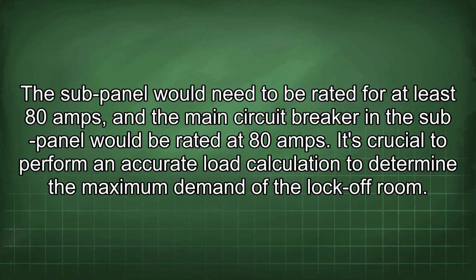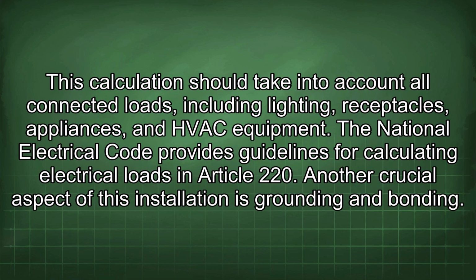It's crucial to perform an accurate load calculation to determine the maximum demand of the lock-off room. This calculation should take into account all connected loads, including lighting, receptacles, appliances, and HVAC equipment. The National Electrical Code provides guidelines for calculating electrical loads in Article 220.